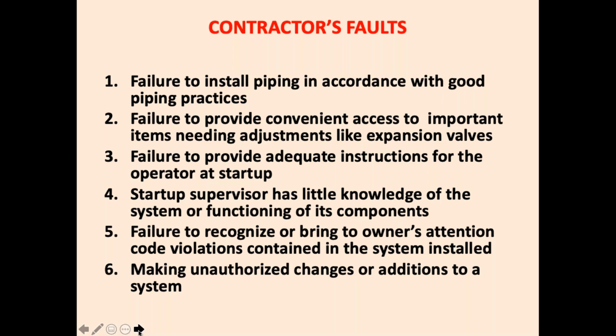Failure to provide convenient access to items needing adjustments, like expansion valves. Now, expansion valves for air coolers may be at 20-meter height, and if you don't have a ladder or a platform to reach that expansion valve, and if the temperature inside the room is minus 20 degrees, no operator will go there, and there could be a problem of attending to those valves. So it is very, very important that space and access should be provided to all the controls which need adjustments.